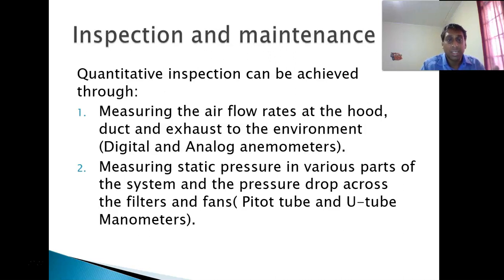So if it's 2 at the face of the hood, that's a capture velocity. It would need to be a little bit more than that to transport it through the hood, especially if you have bends and corners, or worse yet, sharp corners throughout the ducting of the LEV system.